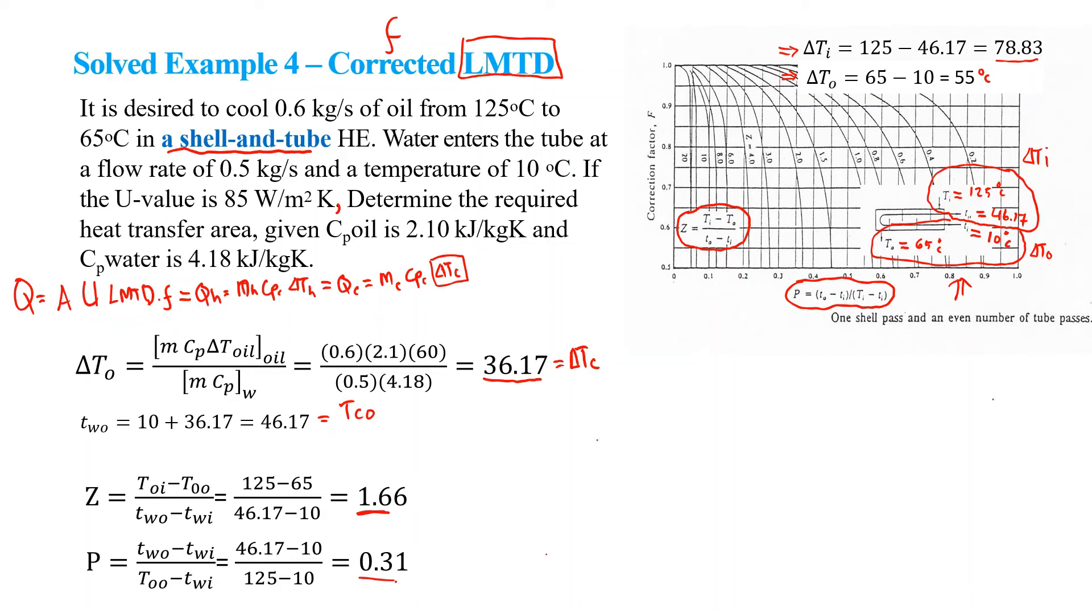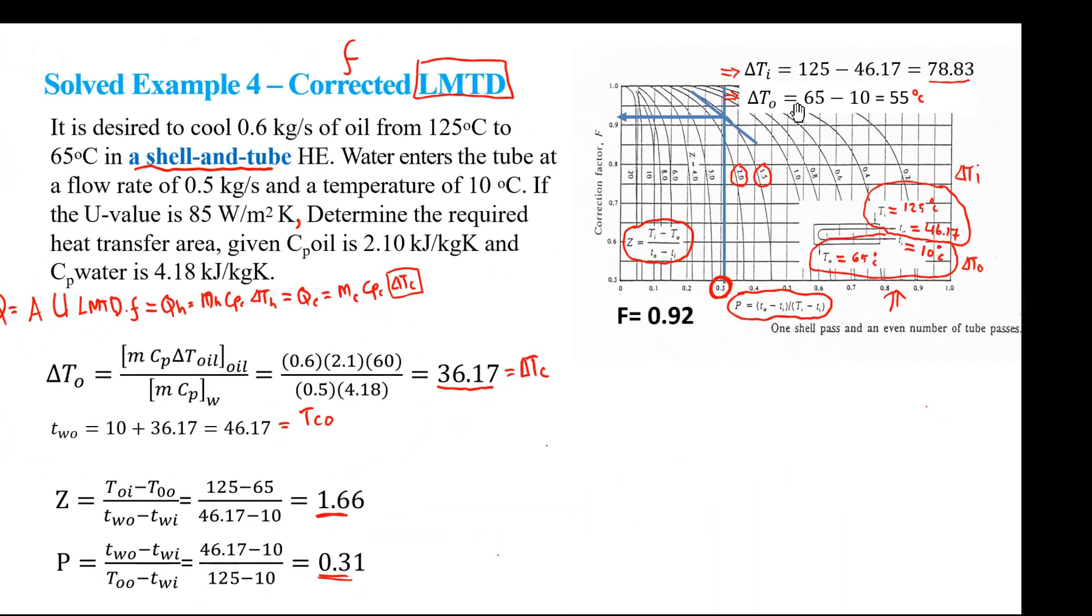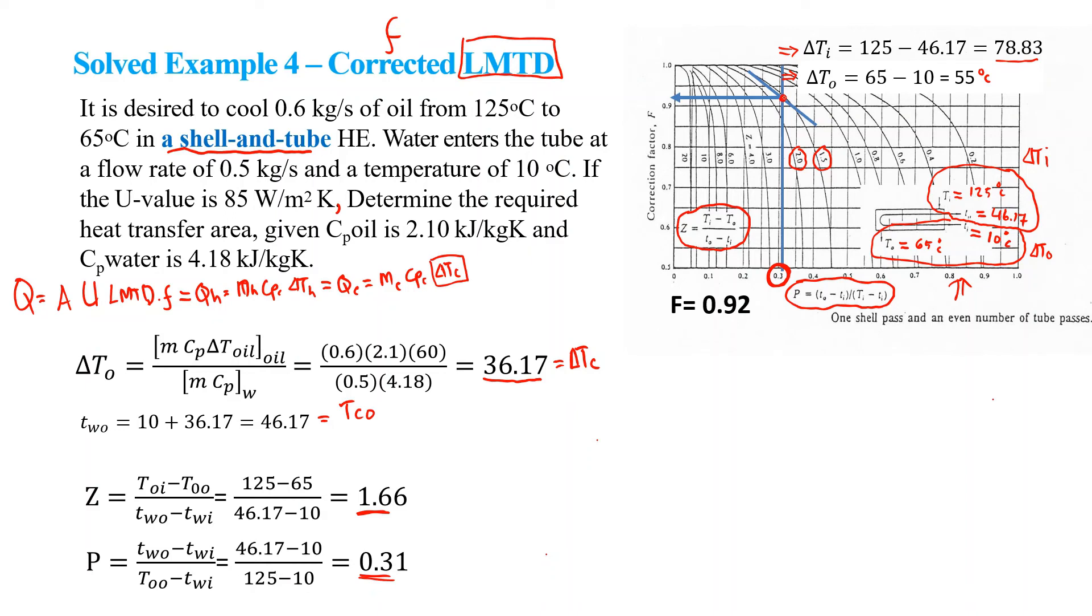We get Z equal to 1.66 and P equal to 0.31. We then try to find out the point where the two values cross. P is about 0.31, and Z is 1.66, which is somewhere between 1.5 and 2.0, very close to 1.5. I identified the point more or less exactly at this point, and you can find out the F value here. The F value I identified as 0.92.